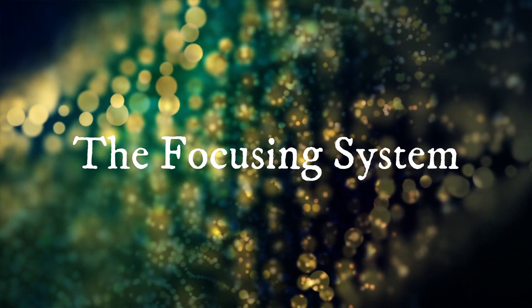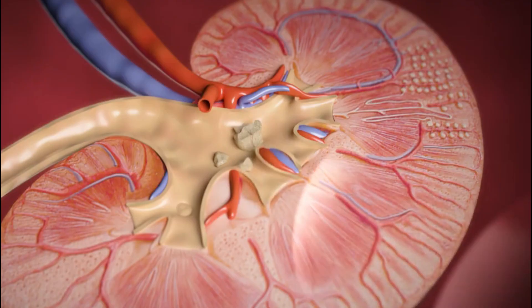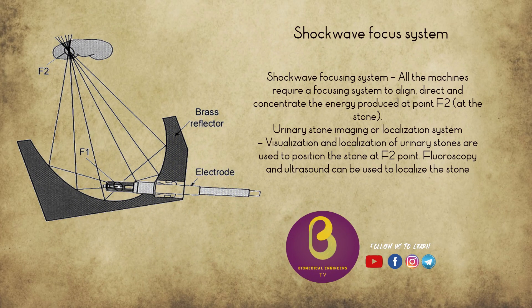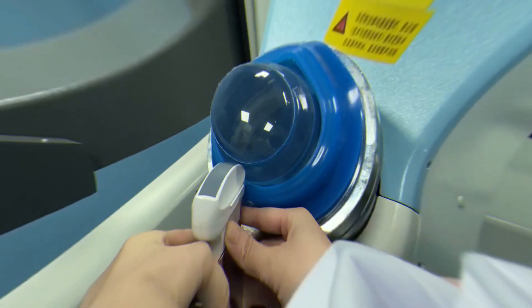The focusing system is used to direct the generator-produced shockwaves at a focal volume in a synchronous fashion. The basic geometric principle used in most lithotripters is that of an ellipse. Shockwaves are created at one focal point F1 and converge at the second focal point F2. The target zone or blast path is the three-dimensional area at F2 where shockwaves are concentrated and fragmentation occurs.